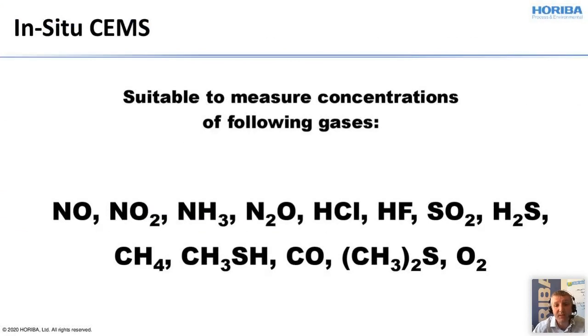The following gases can be measured with in-situ CEMS. It is basically able to detect nitrogen oxides, ammonia, hydrogen chloride, hydrogen fluoride, sulfur dioxide, hydrogen sulfide, methane, methyl mercaptan, carbon monoxide, dimethyl sulfide, and finally oxygen. Depending on other gases available in the gas mixture, it is also possible to detect other gases, but these need to be checked for each application separately.